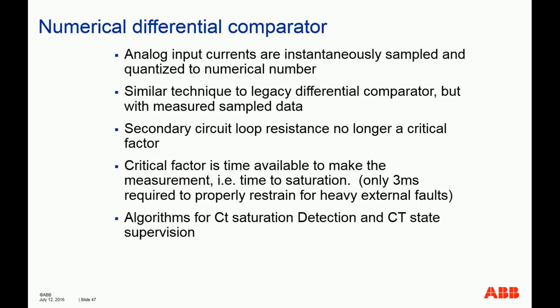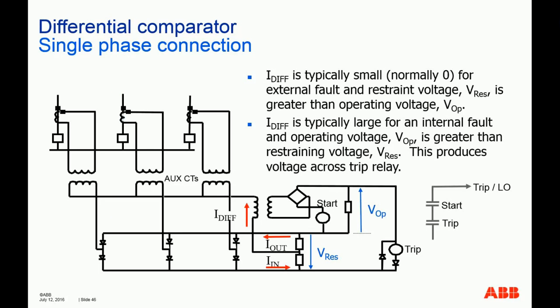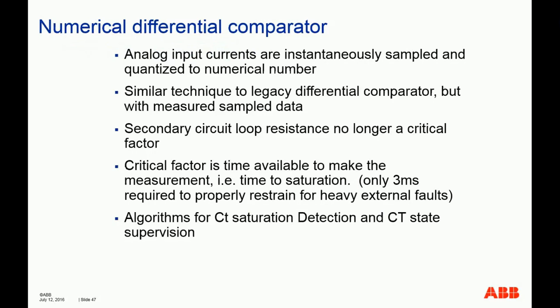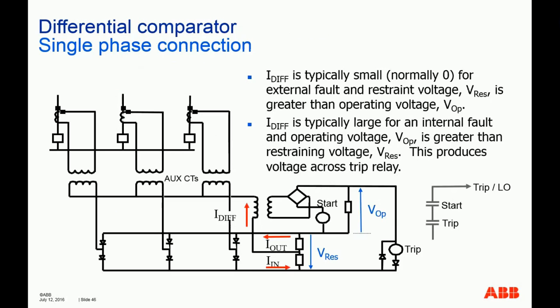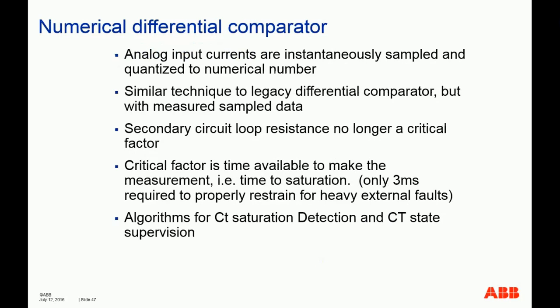Next, we're going over the numerical differential comparators. The same type of relay, same type of principles. You compare the current contributed into the device, and make a decision whether it is an internal fault or external fault. The previous devices used static diode components. Modern relays use numerical calculations to calculate the differential current and compare it with the set slope and pickup settings to decide whether to operate or not.